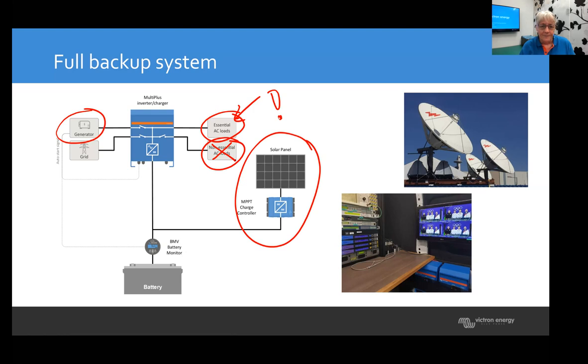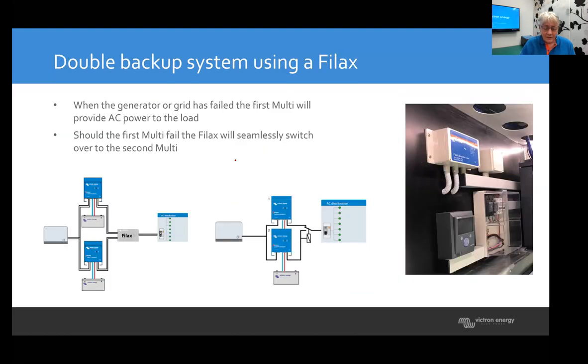So that's that way. And then we have one device called the Filax, and we also have a transfer switch, a different type. The Filax is an automatic transfer switch that has a priority input and a secondary input. As soon as the priority input falls away, it will immediately switch to the secondary input, and when the priority input is back online, it will switch back to that.